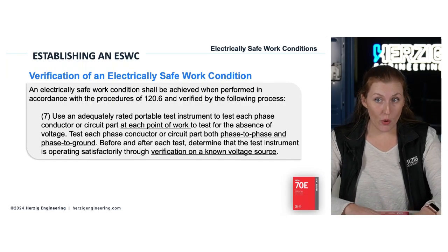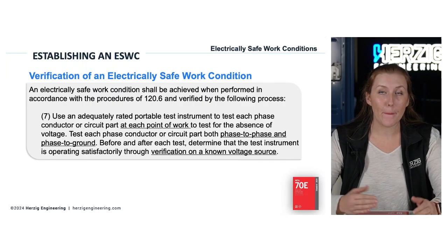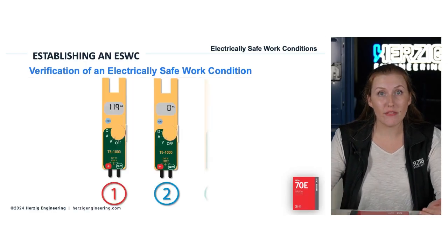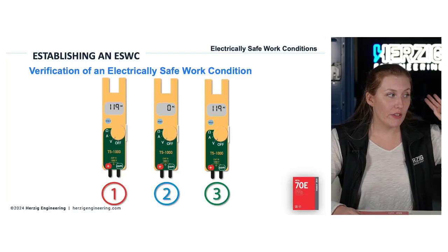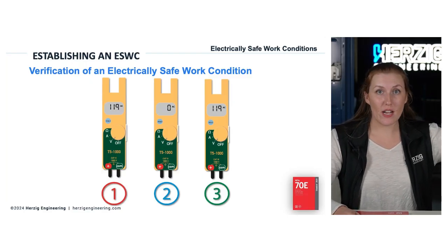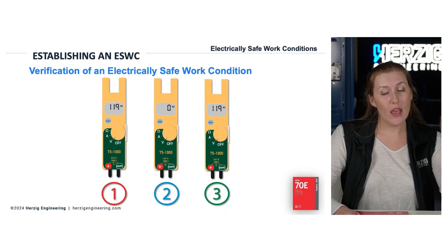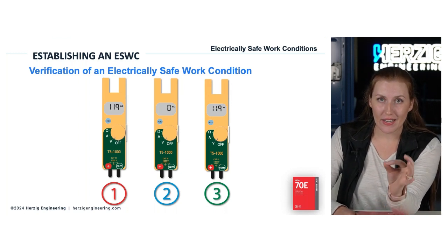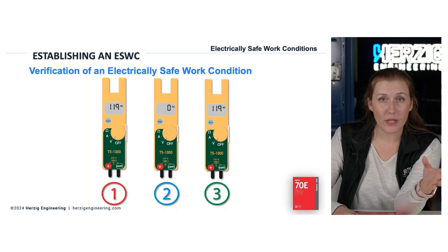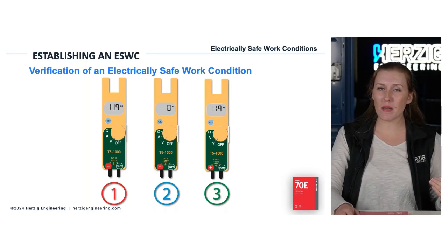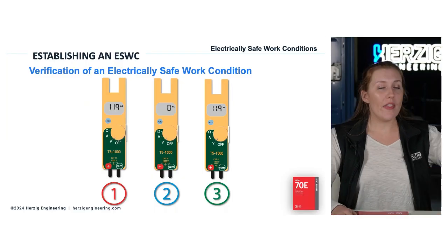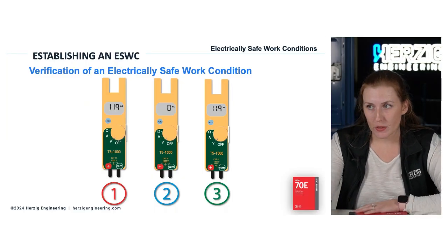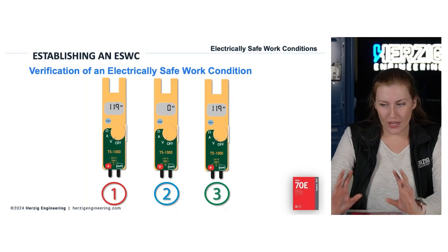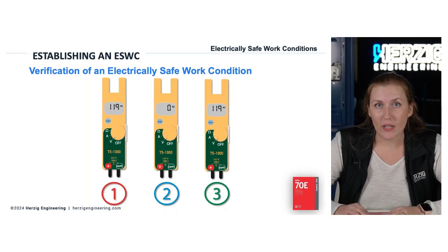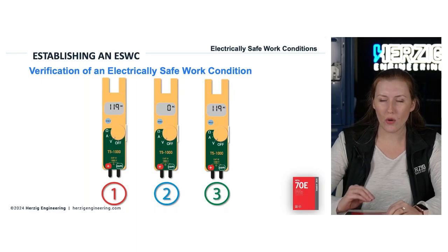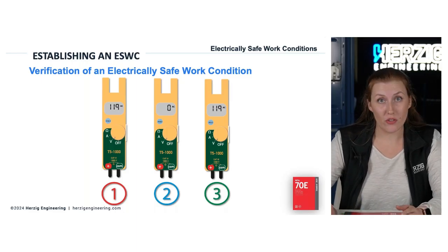So on a known voltage source, they have to make sure the meter is reading properly. That's why it's called live, dead, live. That's a simple way of remembering. I have to go find a known source that's live and energized. My meter reads what I know it's supposed to. Then I'm going to go check phase to phase and phase to ground at each point of work. Hopefully all of that equals 0. Sometimes it doesn't, hence the need for the PPE and the boundaries. Don't assume. And then go back and make sure the meter is still working. Okay? So this issue of thinking something's off when it's not is still so prevalent in a bunch of industries.